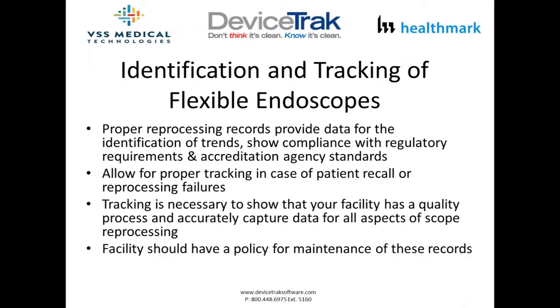Why is identification and tracking of flexible endoscopes important? We need proper reprocessing records that provide data and identification of trends. Those records show compliance with current regulatory requirements and accreditation agency standards. Proper identification and tracking allows for identification of patients in case of a reprocessing failure, which would necessitate a patient recall or infection control outbreak. Tracking is necessary to show your facility has a quality process. You should also have a policy in place on how to maintain and recall these records.